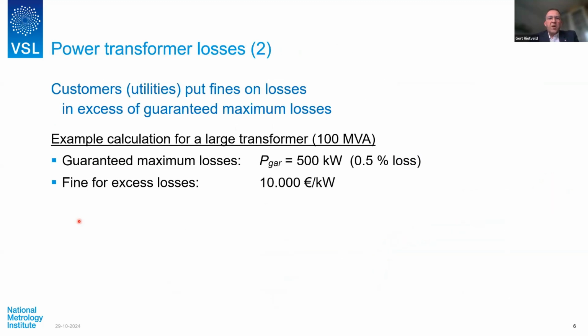And so given this large impact of losses on the cost of ownership, the utilities that buy the transformers put requirements on the losses. So if an actual power transformer has a loss which is above the guaranteed loss by the manufacturer, as part of the contract, they will give a fine to the power transformer manufacturer. And to give an indication of this cost, suppose that we have a reasonably large power transformer of about 100 MVA with a guaranteed loss of 500 kilowatts, or 0.5% loss.